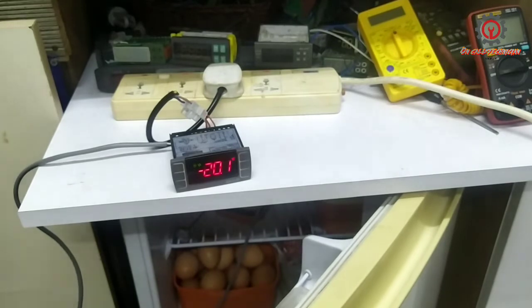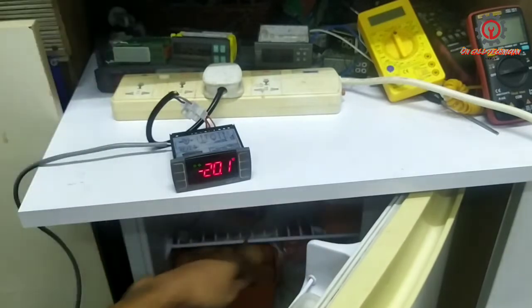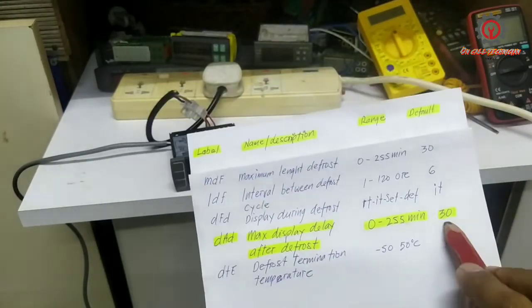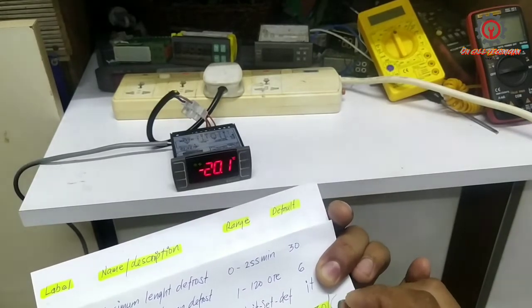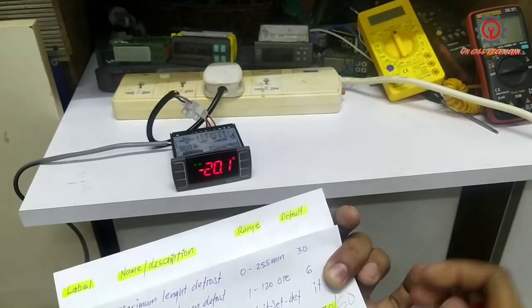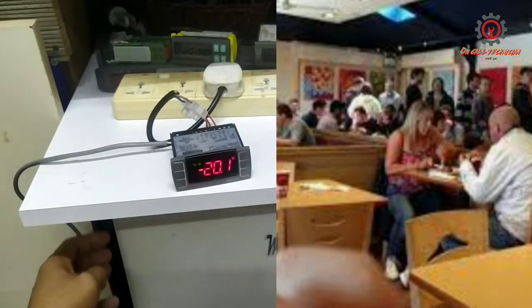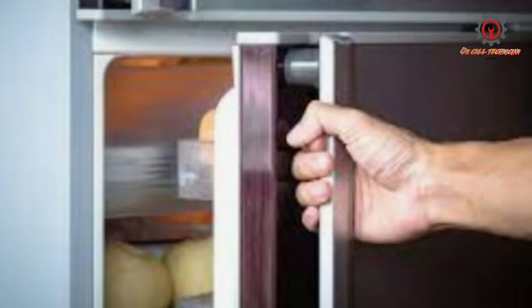Now I'm going to turn this on because the defrost is done. This delay here is not enough, therefore we're going to extend this delay to 60 minutes. Why 60 minutes or one hour? Because during that time, if the restaurant is busy during defrost, are you sure that the people in the restaurant did not open the door to get the product?